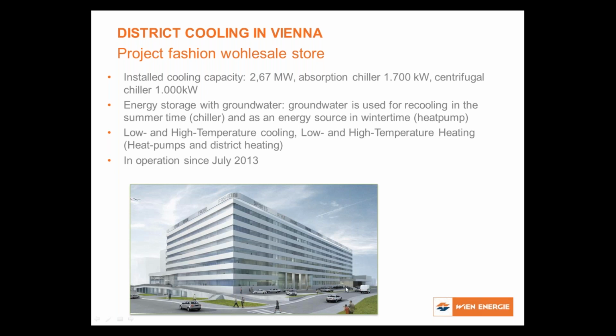During wintertime we switch the chillers to heat pumps, and we use this stored heating energy to heat up the customer. It's actually the biggest geothermal use in Vienna, with 2.6 megawatts of cooling and even more of heating.